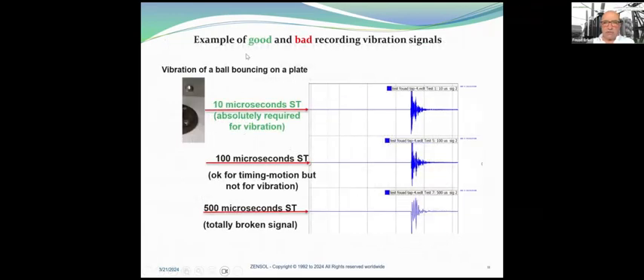And here you have an example of good and bad recordings of vibration signals. If you take a simple vibration of a ball bouncing on a plate, exactly this event has been recorded at 10 microseconds, which is absolutely required for vibration. The same event has been recorded at 100 microseconds. This sampling time is okay for timing and motion, but not for vibration.